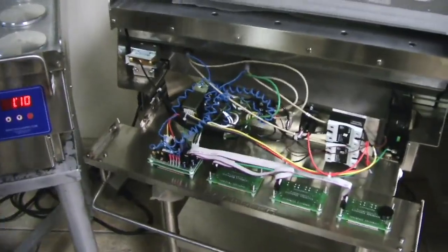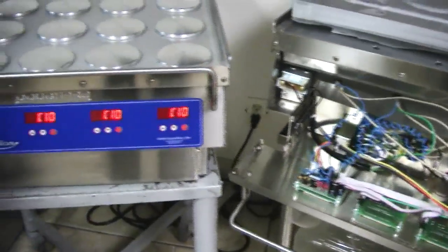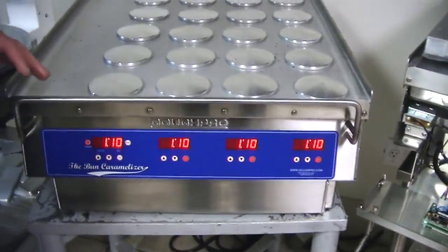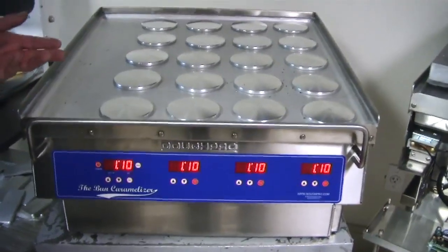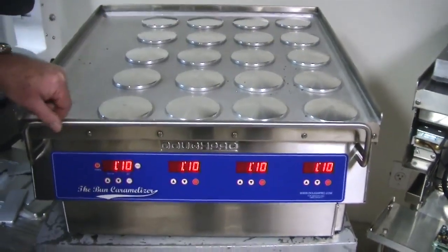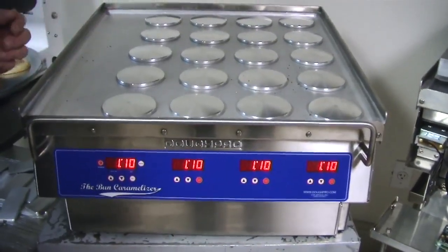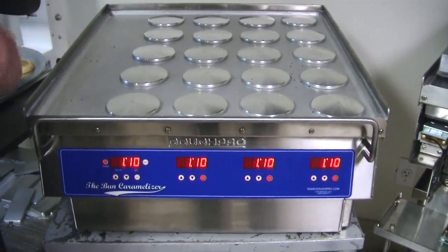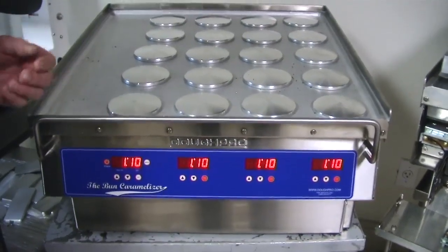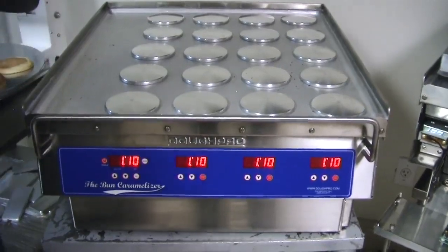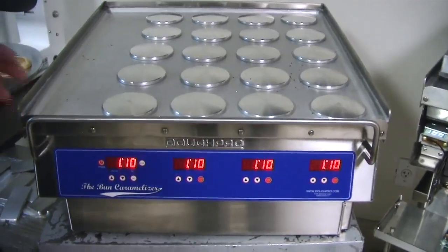It's very important too that when you're testing controls, you make sure the machine heats all the way up. You can't just go 15 minutes. You've got to get this part hot too. The whole thing draws heat. So it's a good 45 minutes before I would even start calibrating this after you've done a fix or have to recalibrate it by setting new offsets. You've got to get this thing up to temperature.